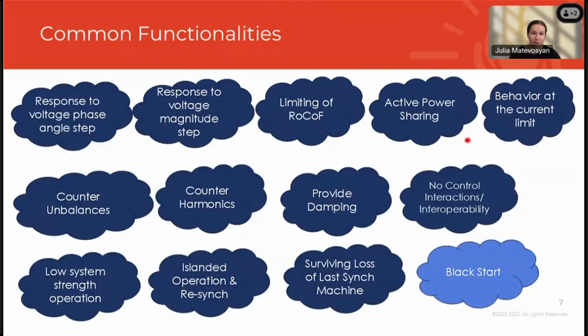Active power sharing behavior at current limit, counter imbalances, counter harmonics, provide damping, no control interactions, and ensure interoperability between all inverter-based resources, operation in low system strengths, operation in an island, and then resynchronization back to grid-connected operation, and then surviving loss of last synchronous machine.